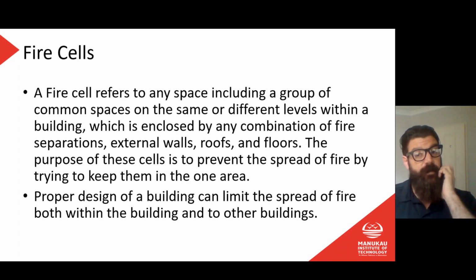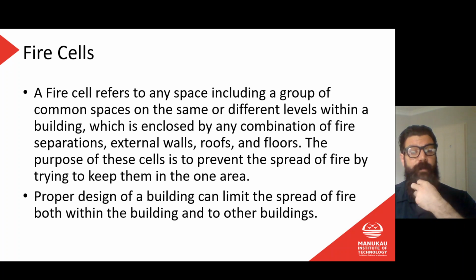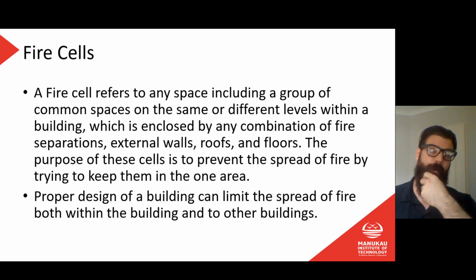So a fire cell refers to any space, including a group of common spaces on the same or different levels within a building, which is enclosed by any combination of fire separations, external walls, roofs and floors. The purpose of these cells is to prevent the spread of fire by trying to keep them in one area. Proper design of a building can limit the spread of fire both within the building and to other buildings.